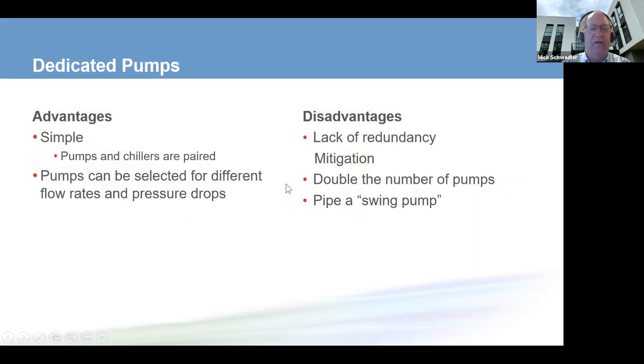Well, when we dedicate pumps to chillers, it becomes simple to operate. The operator goes into this chiller plant. They look at the system control screen. They see chiller A on, pump A on, chiller B off, pump B on. Wait, there's something wrong. Because the chillers and pumps come on in pairs. So it's a very simple way to see whether or not the system is operating well. The other part is when we dedicate pumps, if the chillers have different capacities, therefore different flow rates, and particularly different pressure drops, the pumps can be selected for that specific flow rate and for that specific pressure drop.